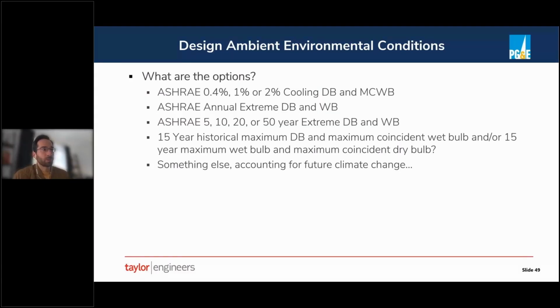So a typical design condition for a non-mission critical facility would be something that we call the ASHRAE 0.4% conditions. On the cooling side, that would mean the ambient dry bulb temperature and the coincident wet bulb that is exceeded for 0.4% of the year. And that makes sense for non-mission critical facilities because we're just dealing with human comfort most typically. And usually it's okay if temperature in a space drifts above, say, 74 degrees for a couple hours a year, because it just slightly impacts human comfort. And if we try to use more conservative conditions, there's a non-linear increase in the cost and size of the mechanical and electrical systems that need to support the space.